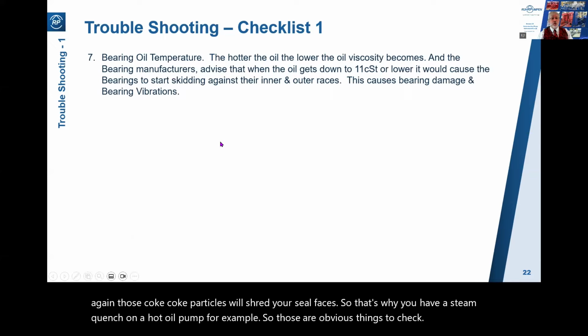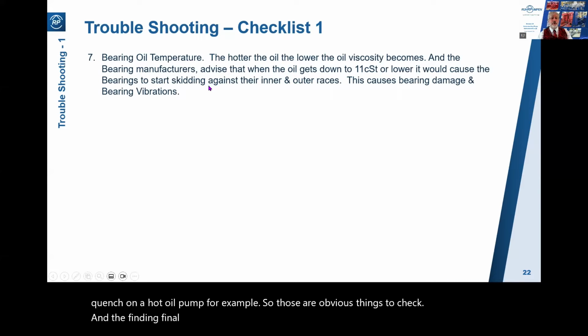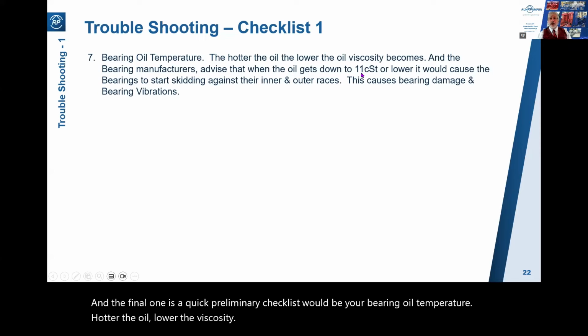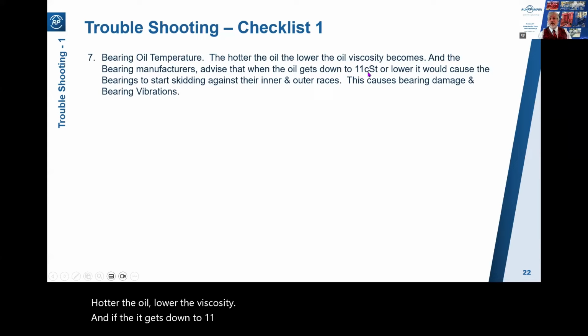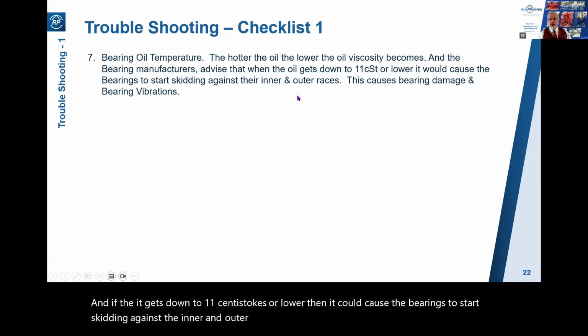And the final one, as a quick preliminary checklist, would be your bearing oil temperature. The hotter the oil, the lower the viscosity. And if it gets down to 11 centistokes or lower, then it could cause the bearings to start skidding against the inner and outer races. Bearing damage, bearing vibrations again.